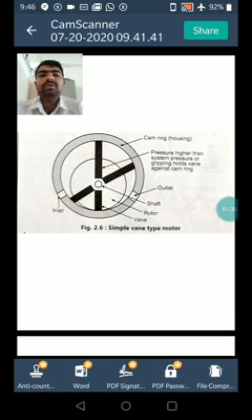A vane motor is a positive displacement unit. The figure shows a vane motor. The rotational unit of the vane motor, known as the cartridge assembly, consists of vanes, rotor and cam ring placed between the two port plates. This is easy for servicing and replacement. For more torque, a rotor with the same outer diameter but a larger exposed vane area can be substituted in place of the original.